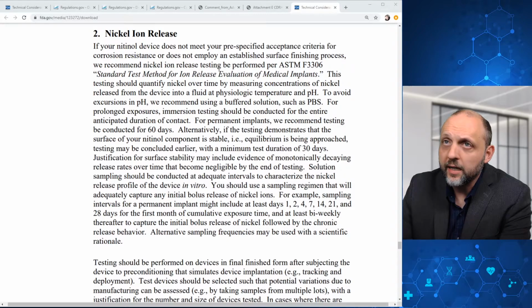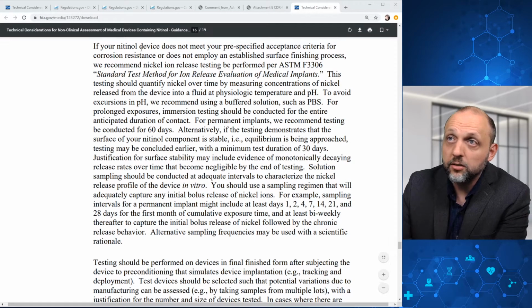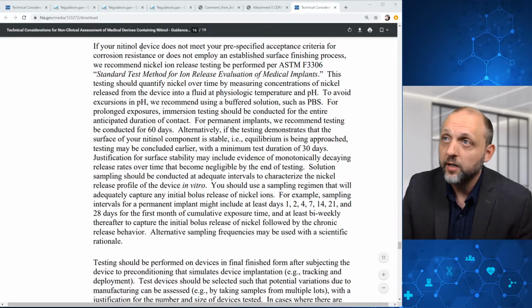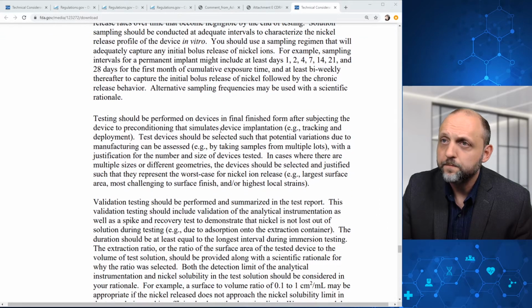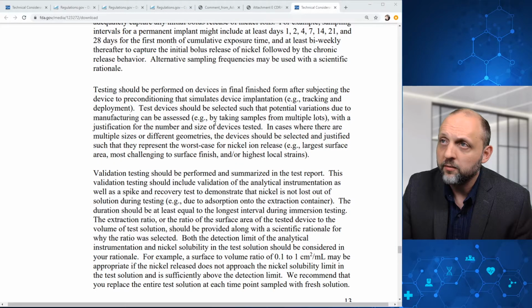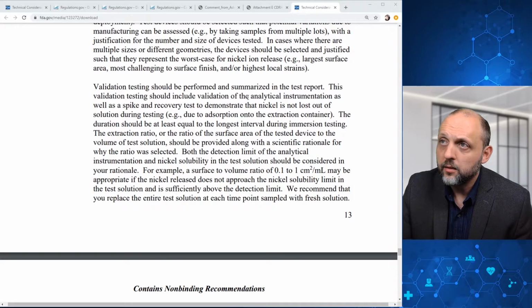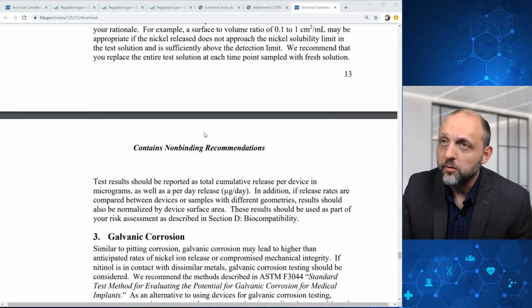And then in terms of nickel ion release, if your nitinol device does not meet your pre-specified acceptance criteria for corrosion resistance or does not employ an established surface finishing process, then FDA recommends nickel ion release testing be performed per ASTM F3306. Some details are included here about what that testing should look like. And again, testing should be performed on devices in final finished form after preconditioning. And again, the validation testing should be performed and summarized in the test report. And there's some additional recommendations.